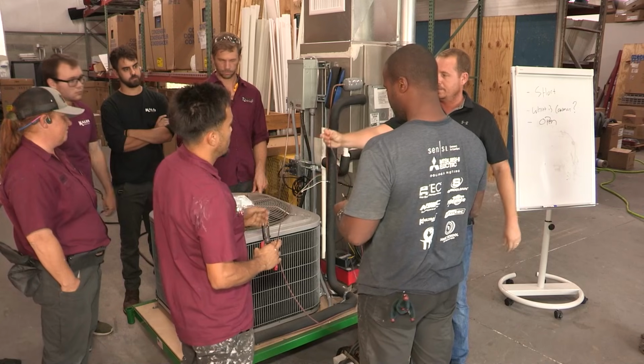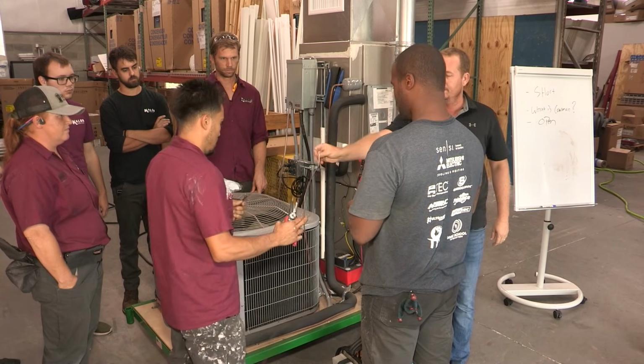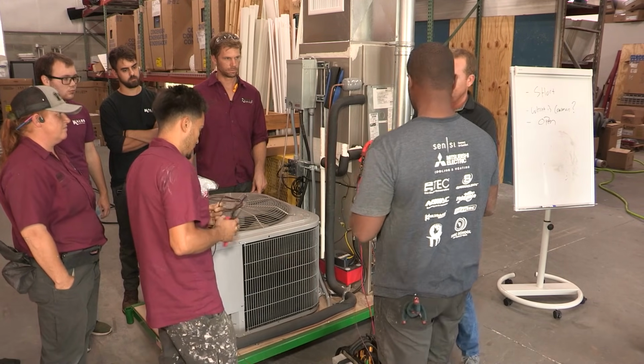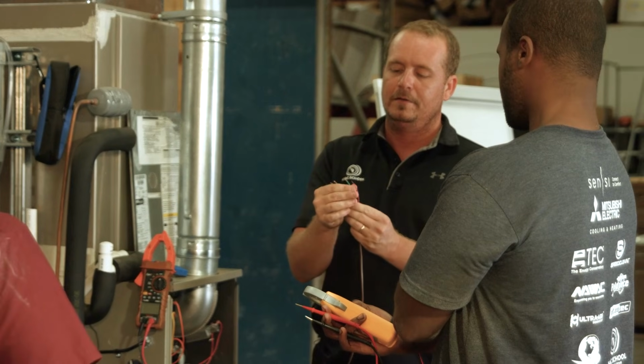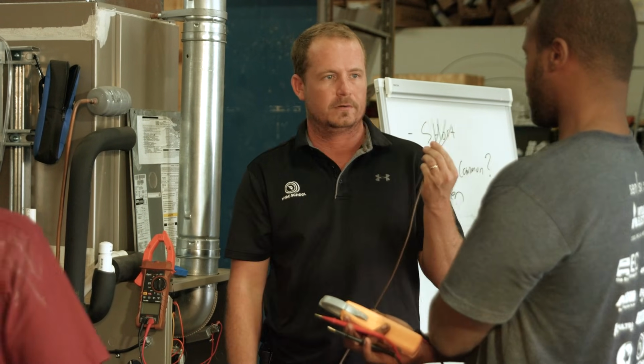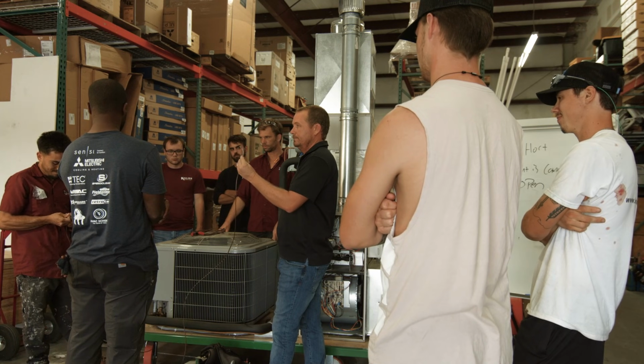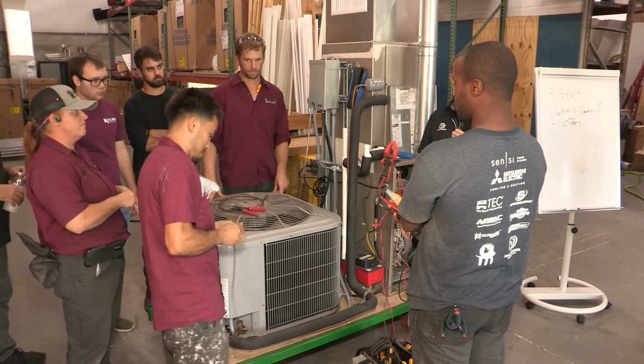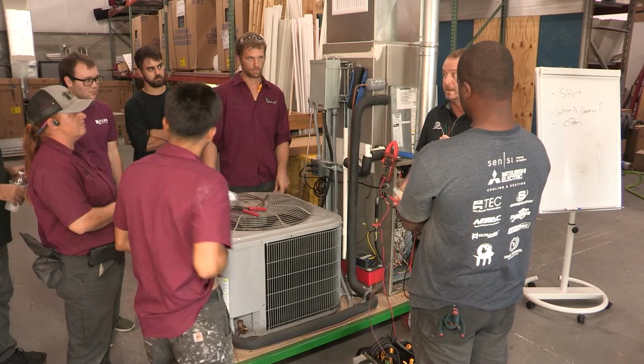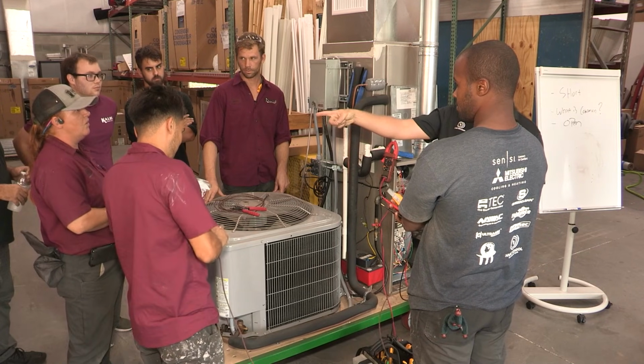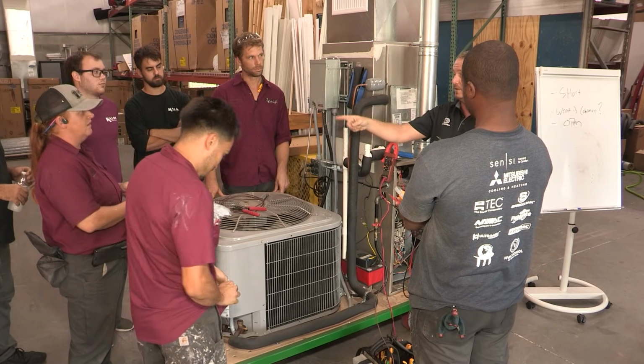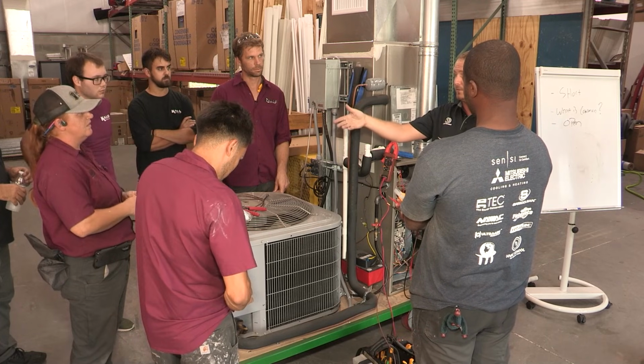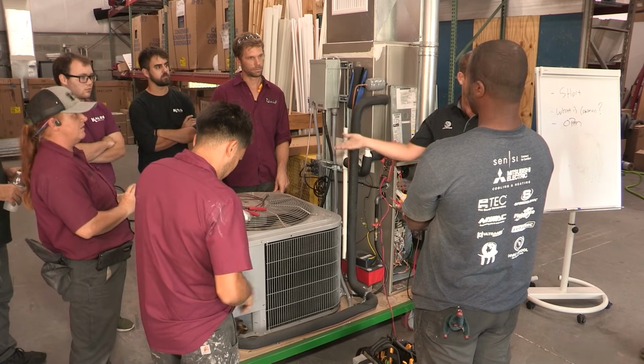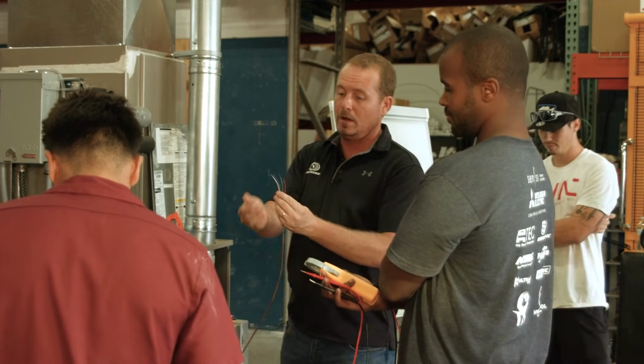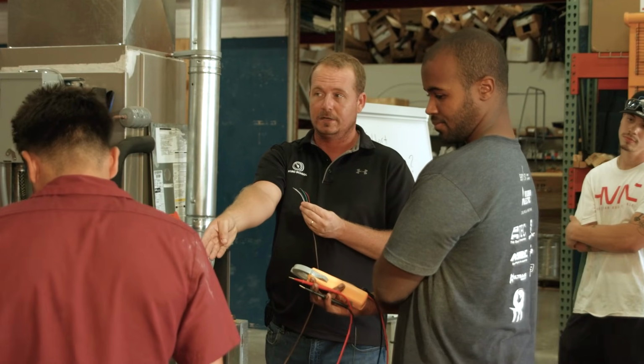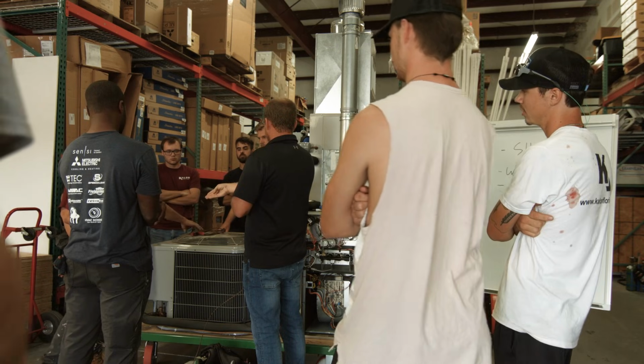Now go ahead and strip off the end here. You don't have to actually measure it, but if I measure right now between any two of these conductors, what am I going to measure with an ohm meter? You're going to measure open or infinite. There's a measurement, but it shows no path, open, infinite ohms. Why? Because on the other end those conductors aren't connected to anything.